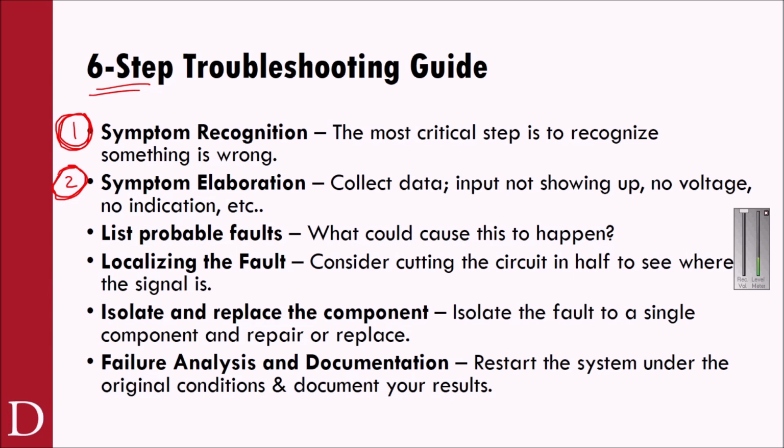It's louder than normal. Something's wrong, because the fact of the matter is, you can troubleshoot it now with a minimal amount of corrective maintenance, fix the problem and have minimal downtime, or you can wait till you burn up a motor, or you can wait till you tear up a bearing, or you break a shaft, or you break a chain or something like that. So it's important that we work with those people to collect the data.